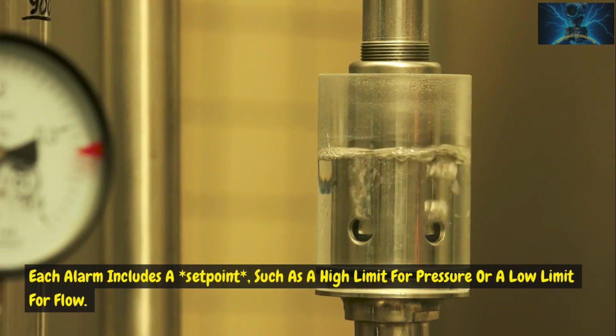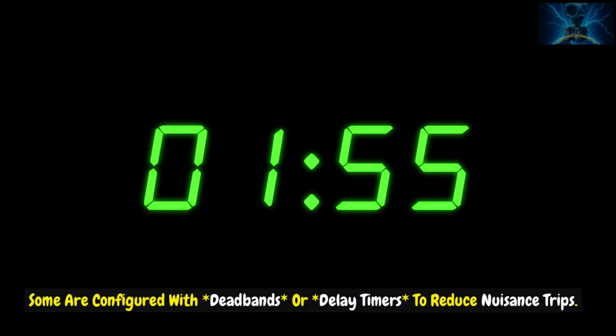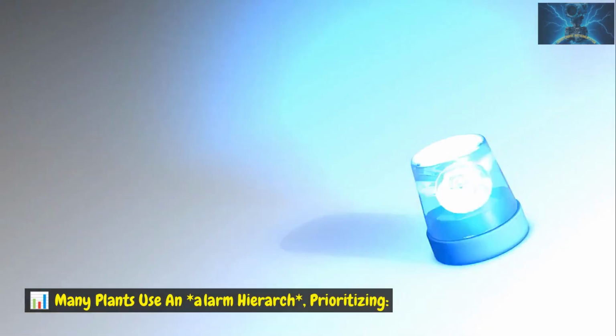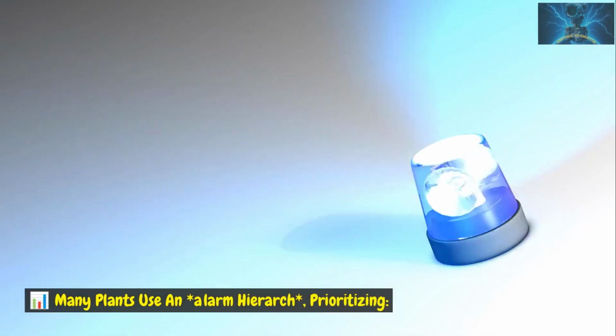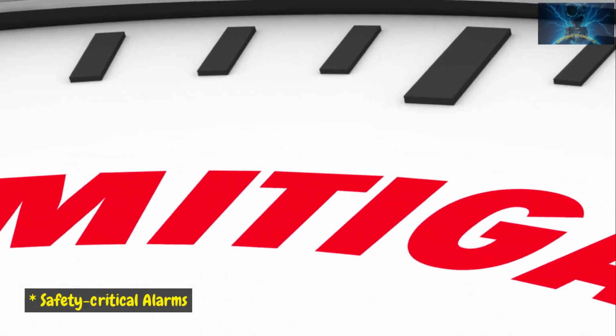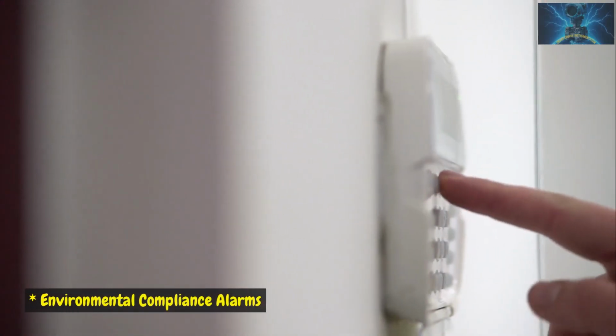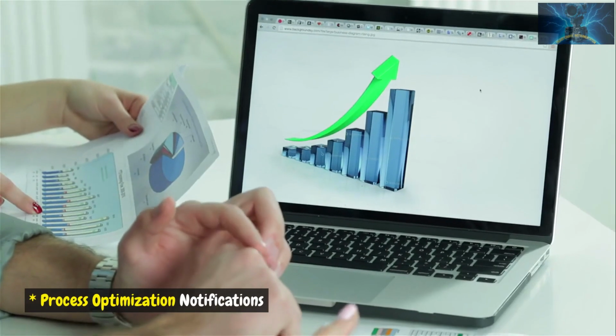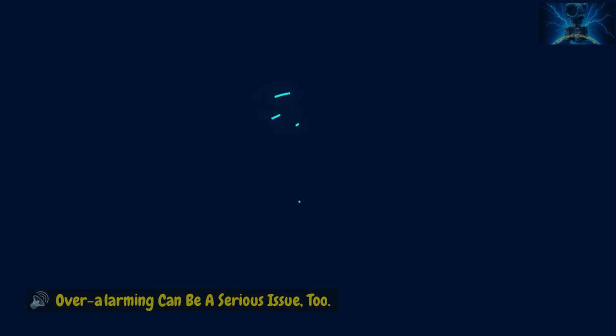Each alarm includes a set point, such as a high limit for pressure or a low limit for flow. Some are configured with dead bands or delay timers to reduce nuisance trips. Many plants use an alarm hierarchy, prioritizing safety-critical alarms, environmental compliance alarms, and process optimization notifications.